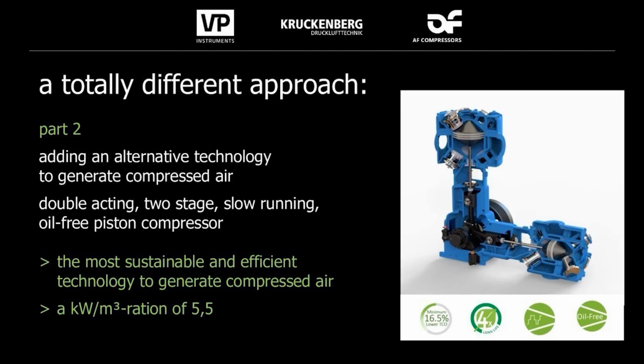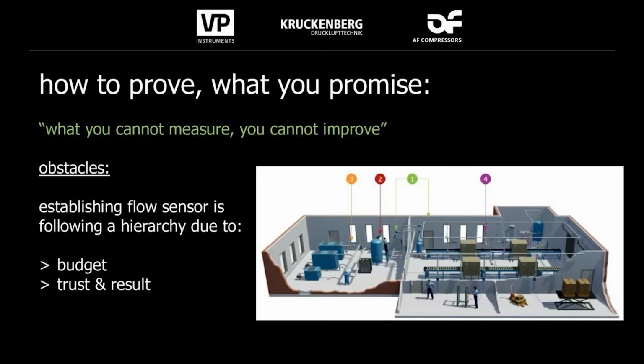So, but how can you establish or how can you prove what you promise? Because we were promising something totally out of the norm, a completely new technology, even if it's old-fashioned technology constantly renewed, but it is not in the general awareness of the decision makers. So you have to establish flow sensors. And normally, if you go to a client, you will not face ideal or perfect situations where you can measure centrally at the compressed air station and see the complete air demand.